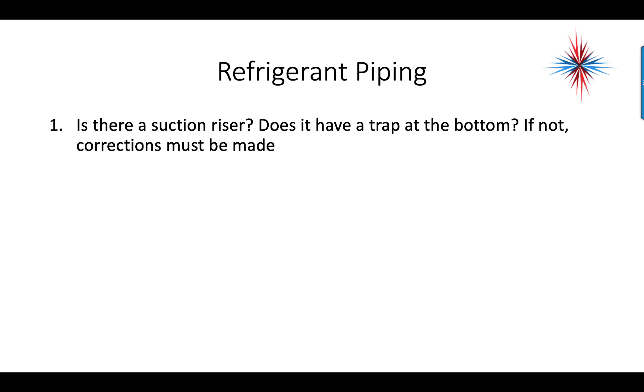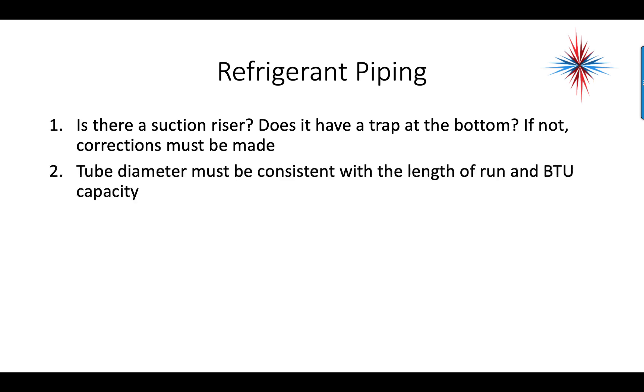We need to take a look at refrigerant piping. Is there a suction riser? Does it have a trap in the bottom? If not, it should. Tube diameter must be consistent with the length of run and the BTU capacity — the more BTUs, the larger the suction line has to be.